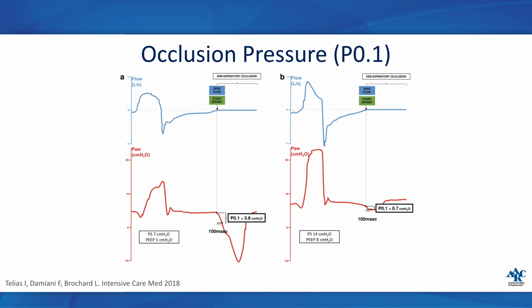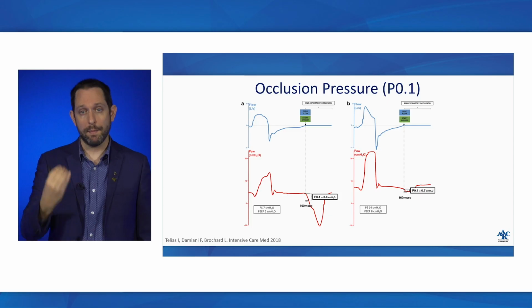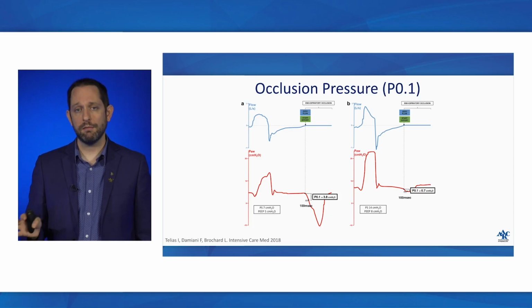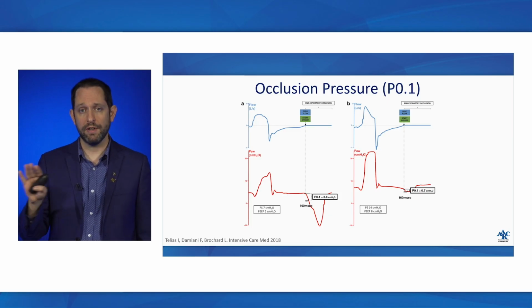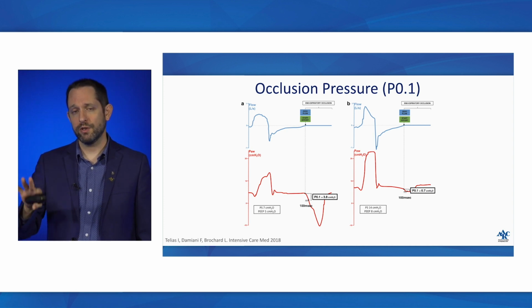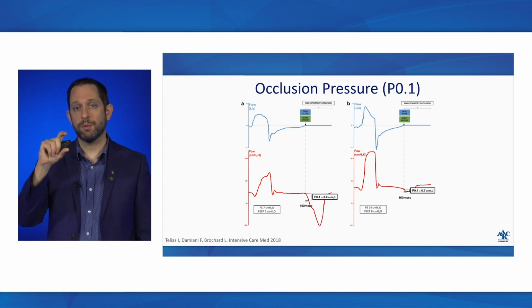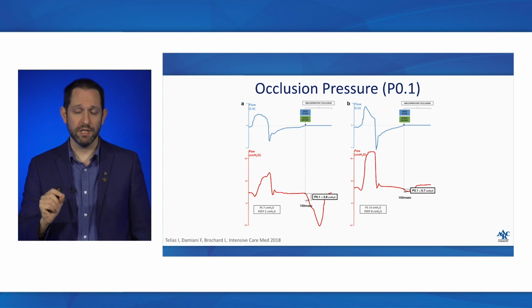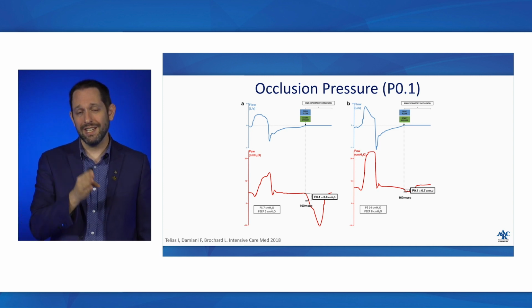One is telling you the change was 3 centimeters of water. The other one was saying, with a negative, that it dropped by 3 centimeters of water. It's the same value. Don't get confused if you use multiple ventilators in your institution. Just understand that that value, that P0.1, is demonstrating how much the pressure has dropped in the first 100 milliseconds of the breath. And it's an indication of drive.